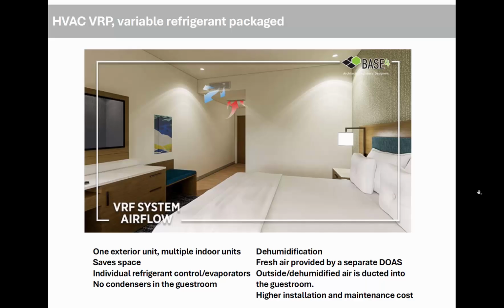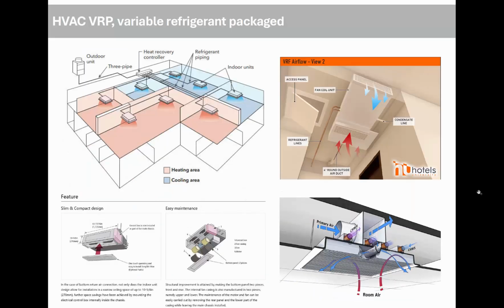Use it to dehumidify the outside air and duct it into the guest room through a separate system. The bonus is that the only thing that you have in here is a little blower fan, and the condenser is not actually in the unit. It's actually outside, and then the refrigerant gets pumped in, and the thermostat controls each individual unit. So here is a version of that, right? So there's the outdoor unit and the pipes, and the refrigerant piping coming in, and the heat for different units depending on what is needed for those spaces.